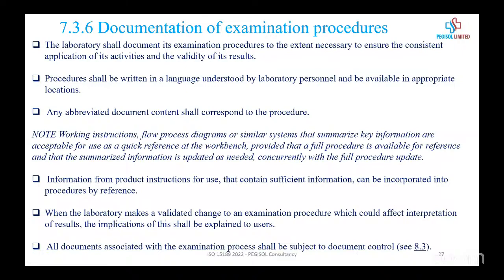Okay, so procedures that should be documented in the lab, in the examination procedures, things like maintenance, calibration, and your QC protocols will need to be documented. Okay, IQCs, quality control, your calibration, including even your reagent usage.